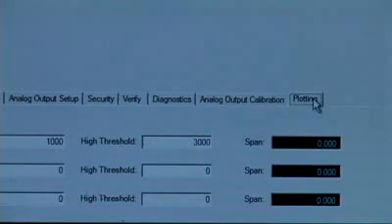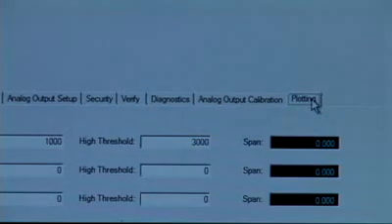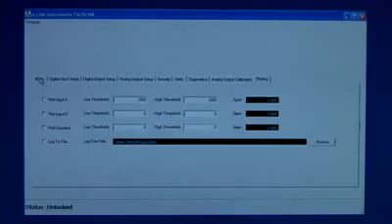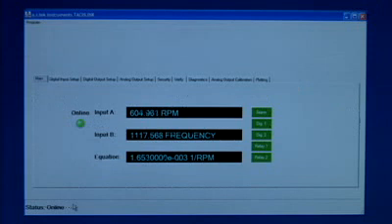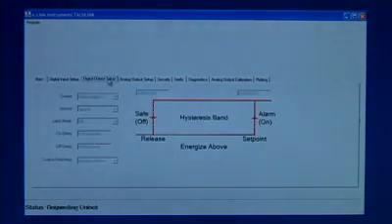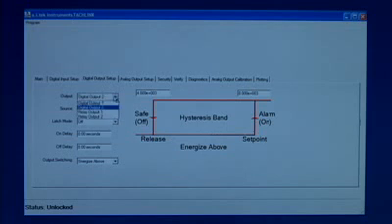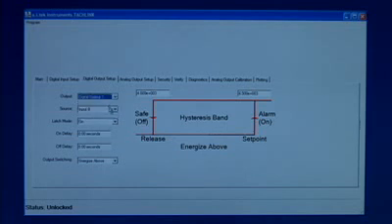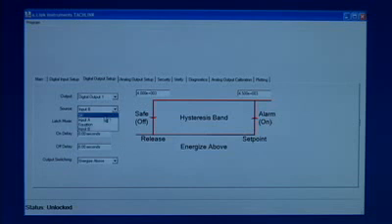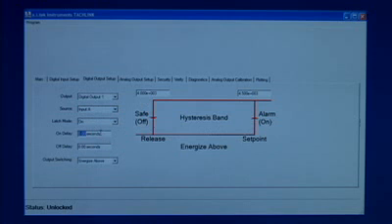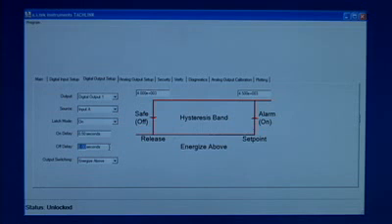We will again set up digital output 1, this time using TAC-Link. Click on the digital output tab. Tab to the output pull-down menu and select digital output 1. Tab to the source menu and select input A. Tab to latch mode and select ON. Tab to ON delay and change from 0 to 2.5. Tab to OFF delay and leave it 0.